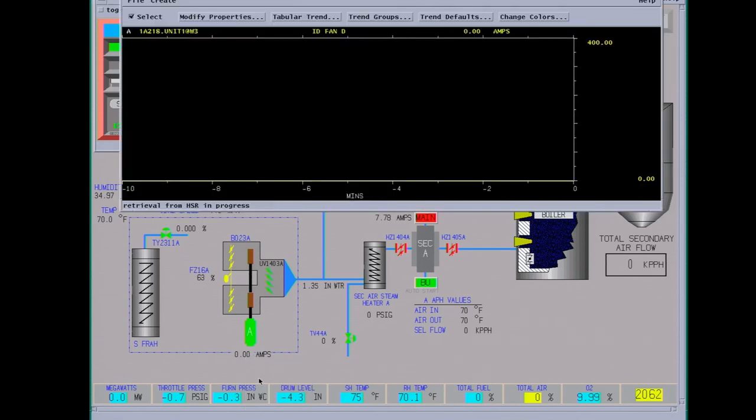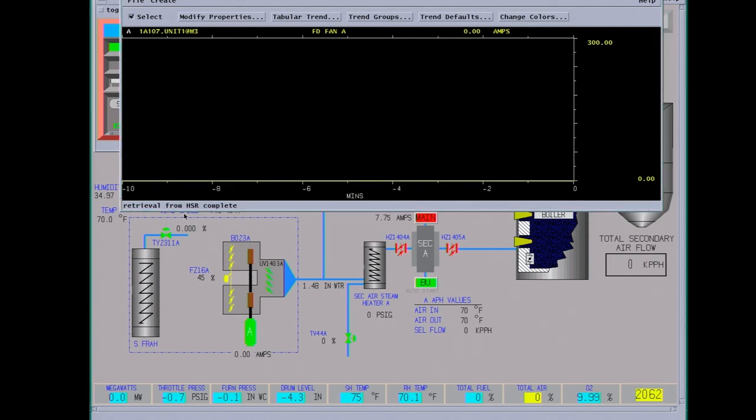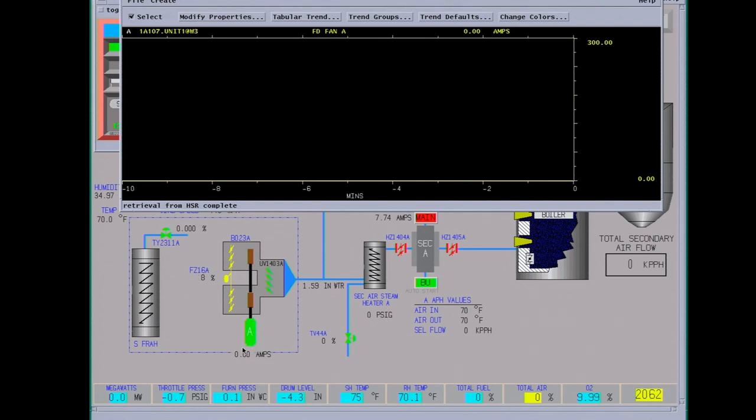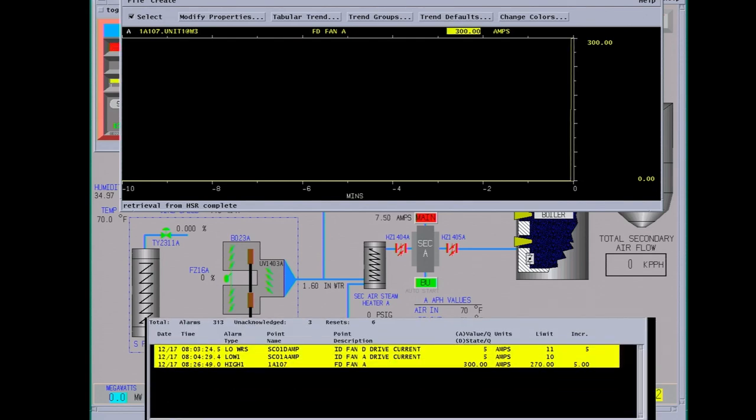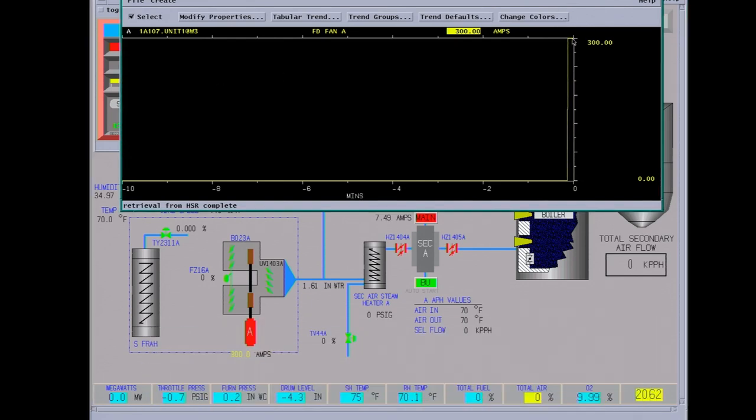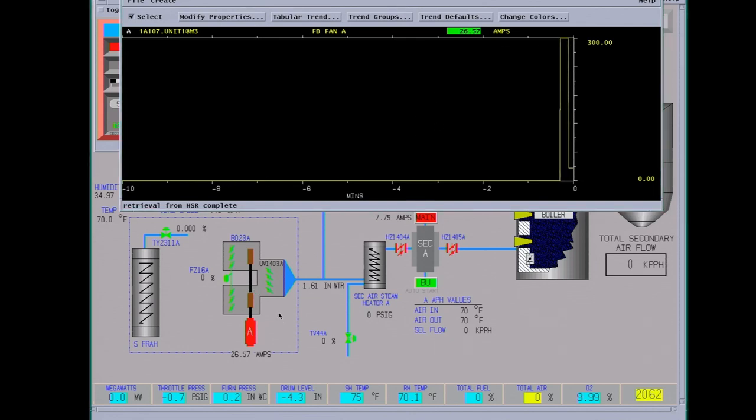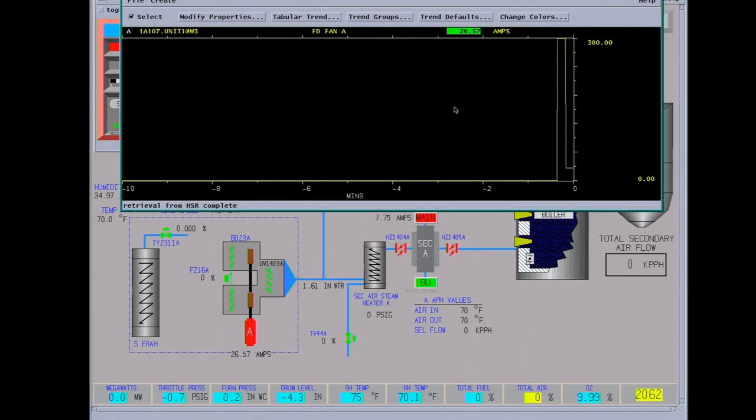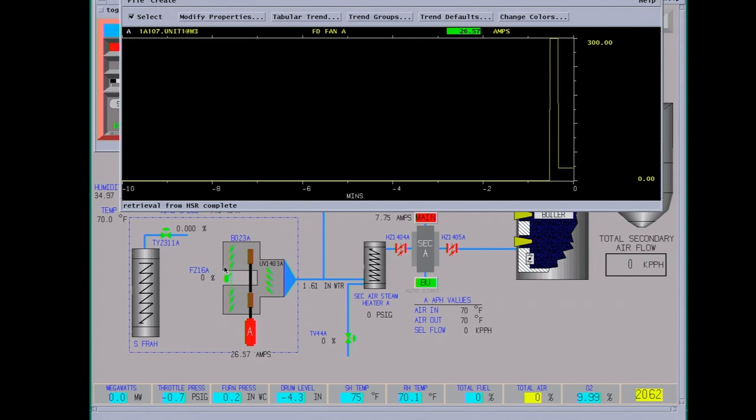We'll throw a quick graph up here. There's a tremendous amount of heat developed when these large motors start. Okay, the outlet damper is closed, the inlet is driving closed. This will swing the plant power pretty good. Both dampers are shut now. It just started, pulling 300 amps. 300 amps is all the more the gauge goes, it's actually a little bit more than that. You can see it come up over here. Should take less than 15 seconds for it to start dropping. So if it stays at high current more than about 15 to 20 seconds, should probably trip the motor. Okay, it's running. The dampers are closed. Allows the motor to run a little bit and cool down from the starting inrush current.